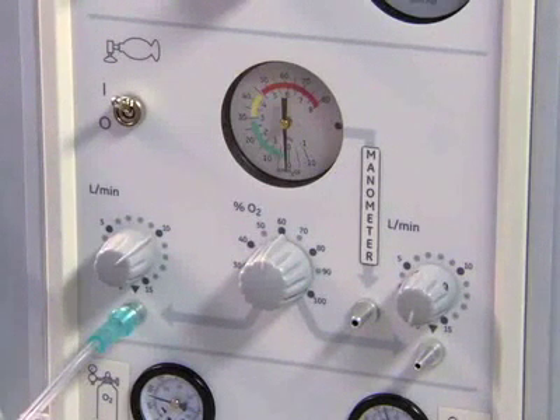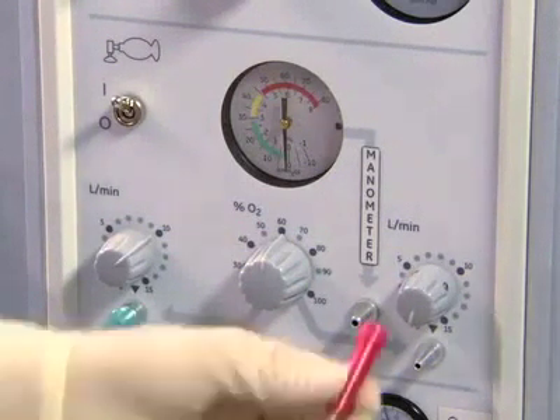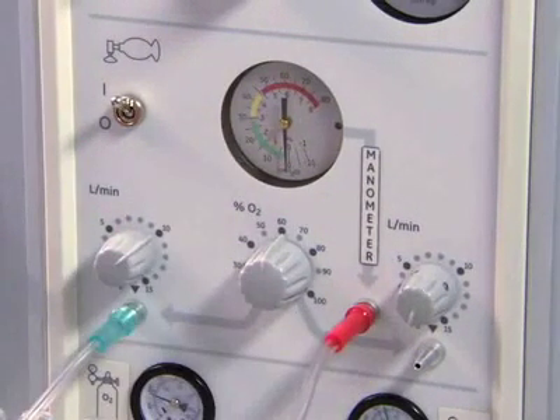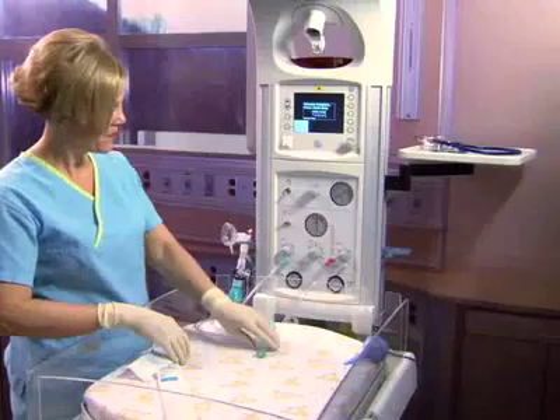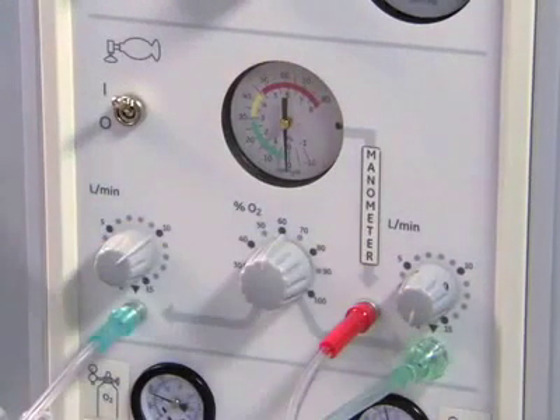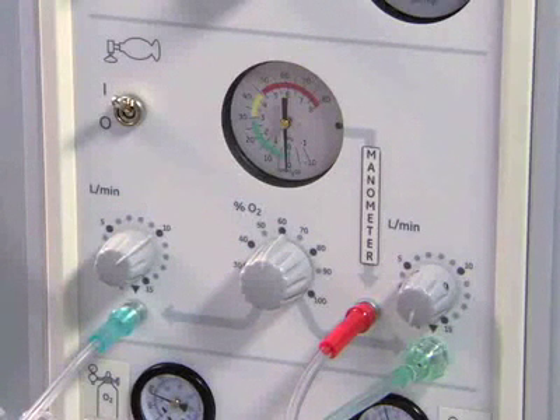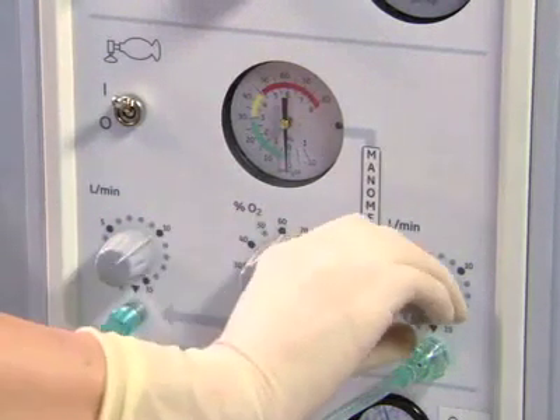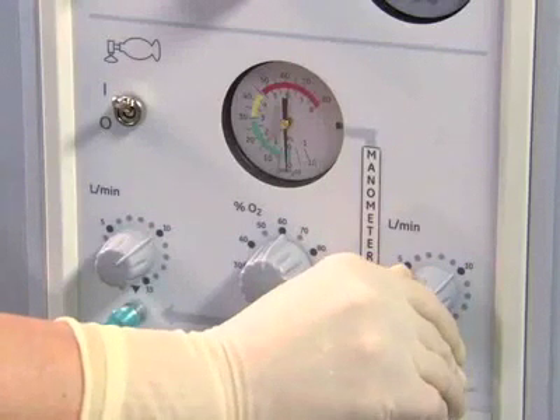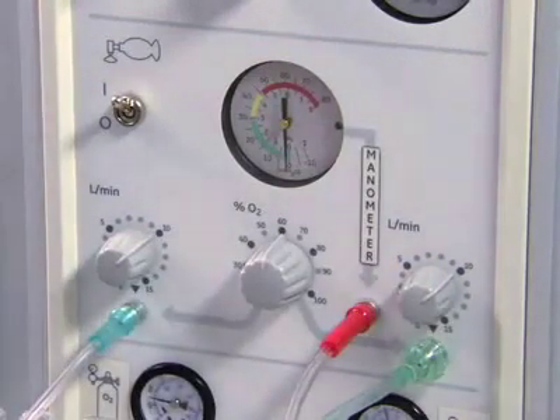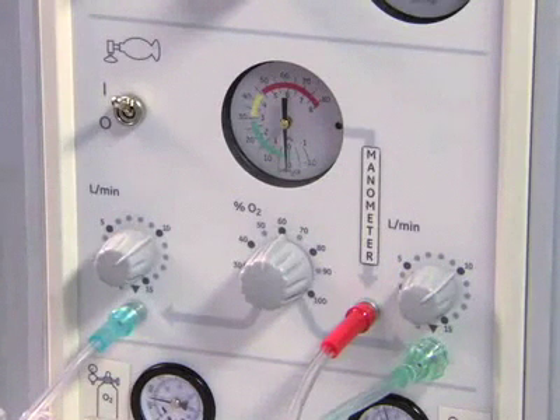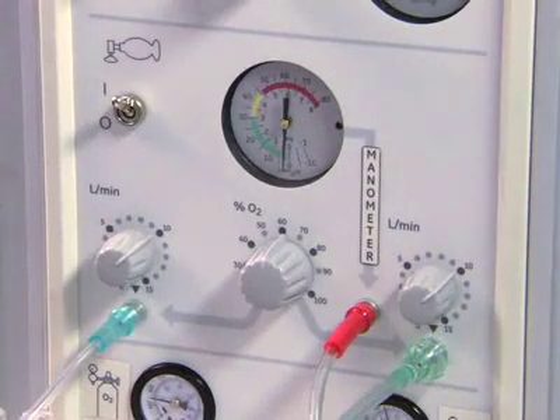Connect the pressure tubing from the resuscitator to the pressure manometer connector on the front of the resuscitation system. You may omit this step if you are using a manual resuscitator with an integrated manometer. Use oxygen tubing to connect either a self-inflating or flow-inflating manual resuscitator to the right gas outlet on the front panel of the resuscitation system. Adjust the flow meter control knob above the outlet to a desired flow rate between 5 and 15 liters per minute. 10 liters per minute is effective in most cases.